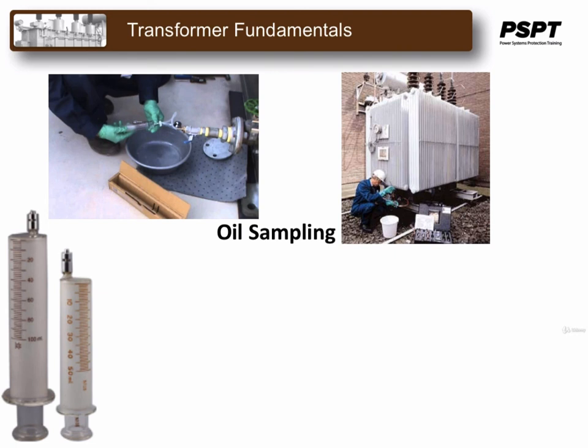There are a number of environmental variables such as temperature, precipitation, etc., to consider before collecting a sample. The ideal situation for collecting a sample from an electrical apparatus is 95 degrees Fahrenheit or 35 degrees Celsius or higher. 0% humidity and no wind would be very helpful as well. Cold conditions or conditions where relative humidity is in excess of 70% should be avoided, as this will increase the moisture in the sample. Collecting a sample during windy conditions is also not recommended because of dust and debris that could enter the sample easily and disrupt accurate particulate counts.